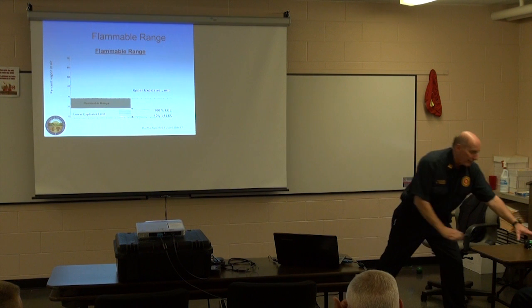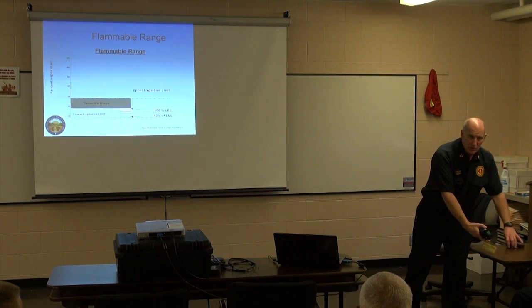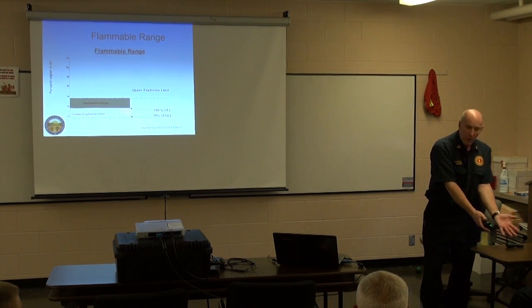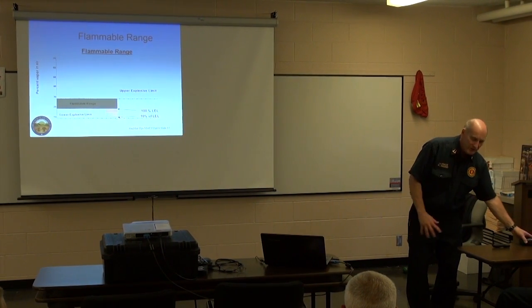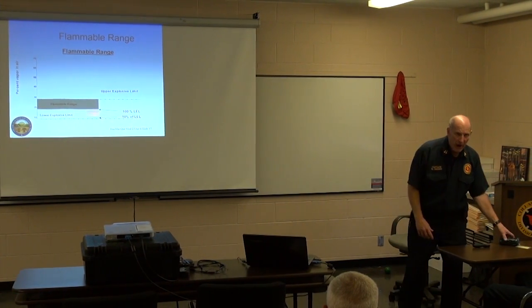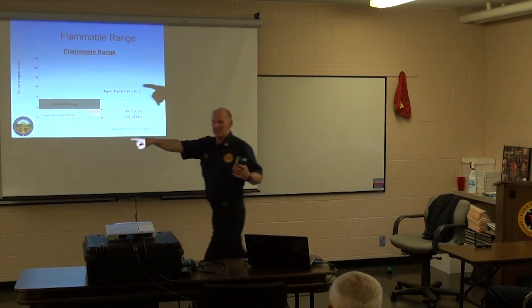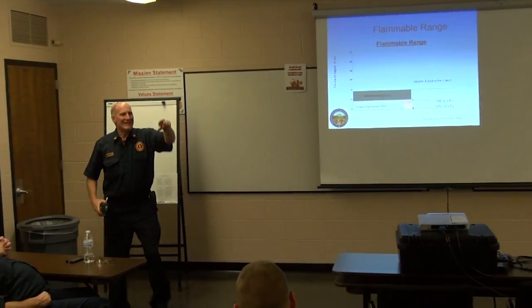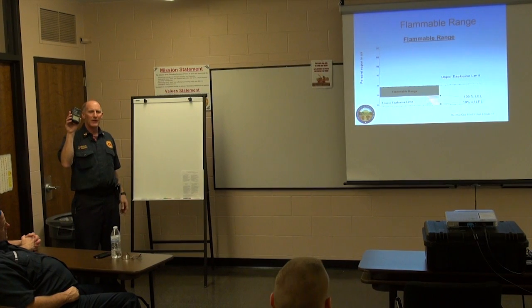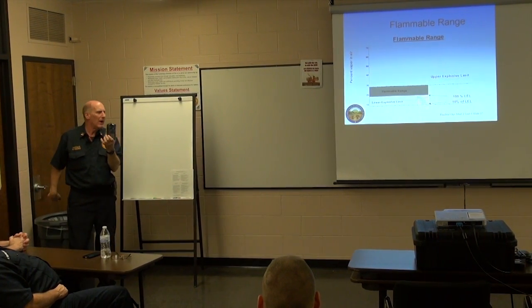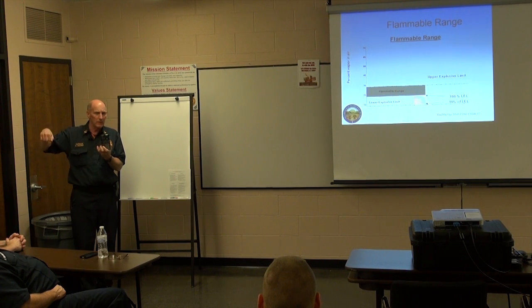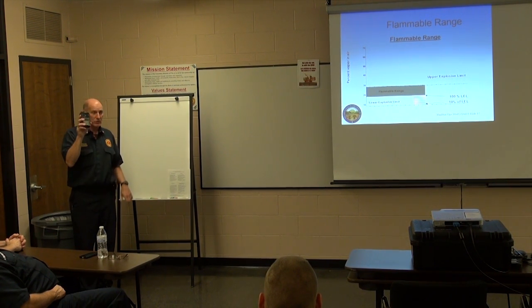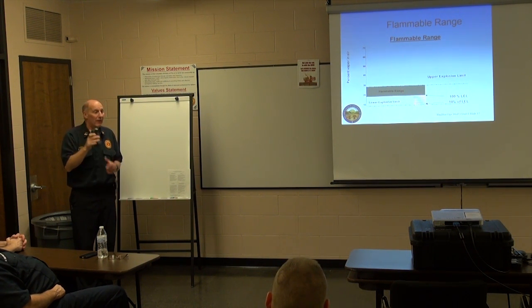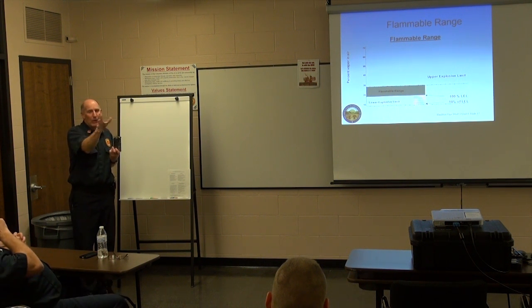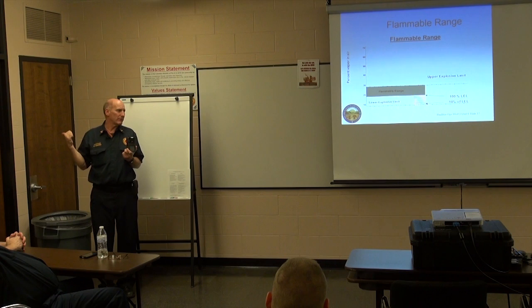If I'm measuring a flammable atmosphere and I'm 6 inches away from it before I get a reading of 1 or 2 or 10, great, put the monitor aside and clean up the mess or shut the valve off. But if I'm standing at this door and my gas leak is clear over there in the corner and I'm getting a reading of 1 here at the door, I'm guaranteeing you someplace between here at the door and where that leak is occurring is 2 and 3 and 5 and 10% and 90% and 100% of the LEL. And if the ignition happens back at that point, it's going to blow you back out the door.